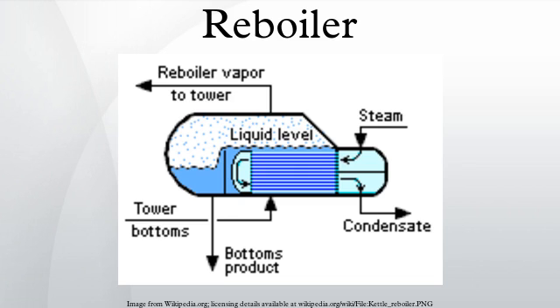Reboilers are heat exchangers typically used to provide heat to the bottom of industrial distillation columns. They boil the liquid from the bottom of a distillation column to generate vapors which are returned to the column to drive the distillation separation. The heat supplied to the column by the reboiler at the bottom of the column is removed by the condenser at the top of the column.